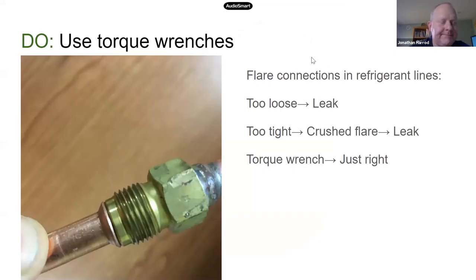So one of the things that I've been really talking and writing a lot about lately is refrigerant leaks. Refrigerants are what make heat pumps work. They absorb heat and they release it very efficiently depending on the pressures that are created in the system. So they can move heat into the house in the winter and out of the house in the summertime. The problem is that if refrigerants leak out, the system doesn't work. And if they get into the atmosphere, they themselves are very potent greenhouse gases. The ones that we use today have global warming potentials several hundred to a thousand times the same amount of carbon dioxide. So for a lot of reasons, we want to make sure that these refrigerant lines are 100% tight.